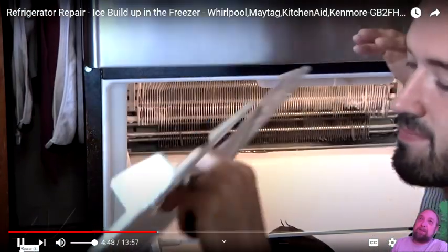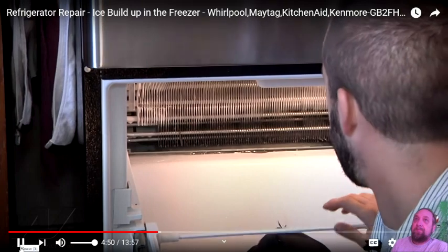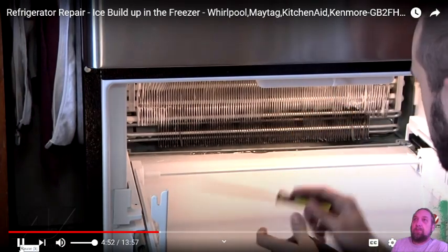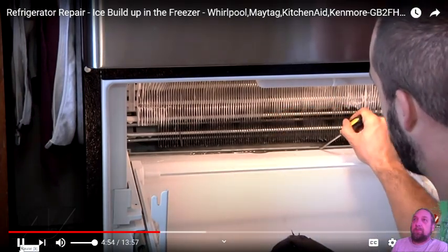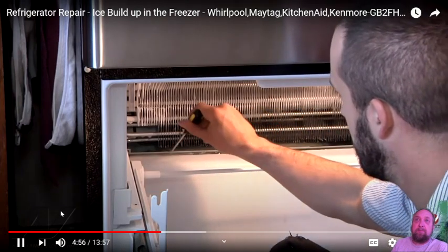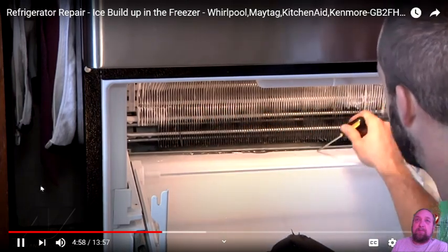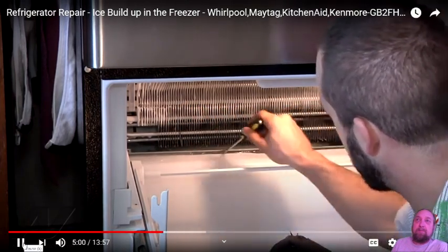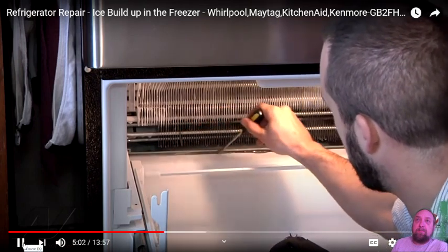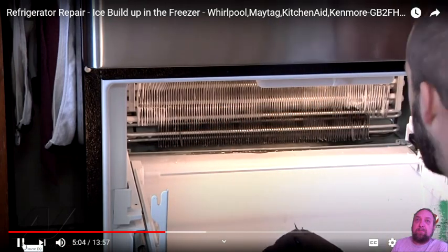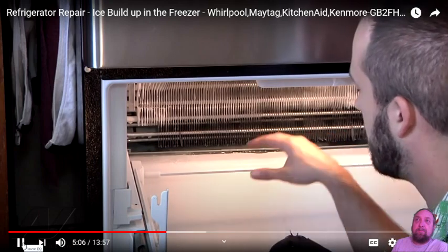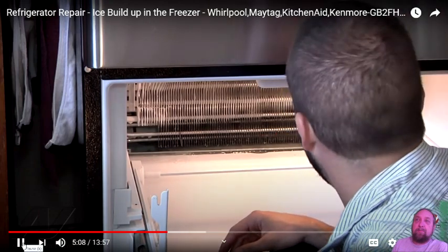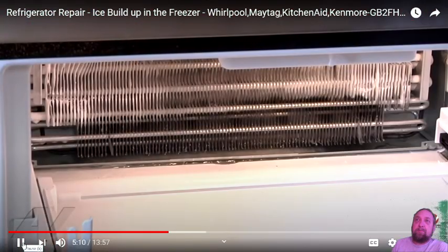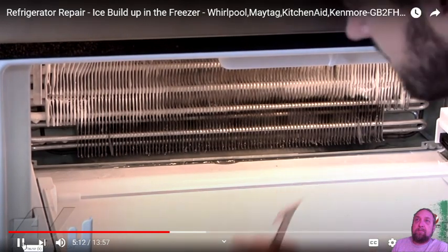Just like that. And as you can see, we've got a buildup of ice underneath this drain pan here. Looks like it's probably just got done defrosting, or just started a defrost cycle. There's a lot of water back there. But we're just going to break up all that ice, and then we're going to replace the drain grommet.